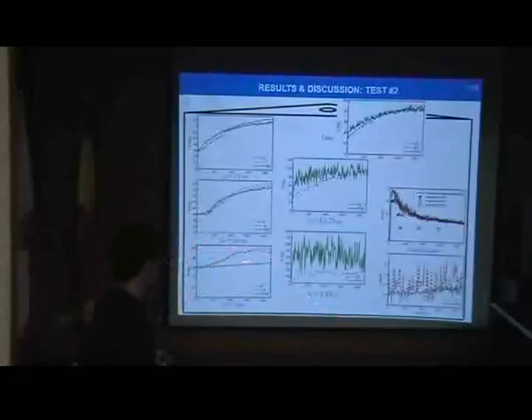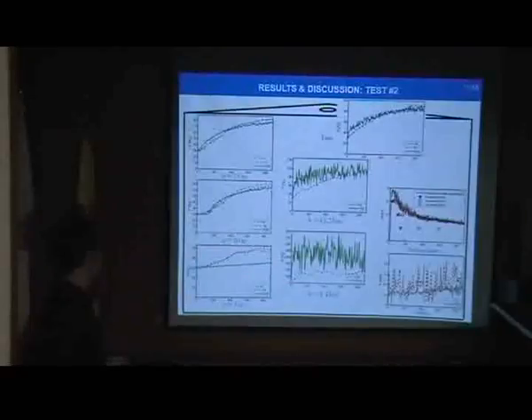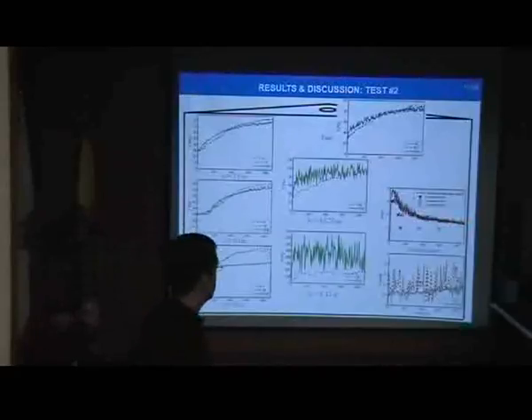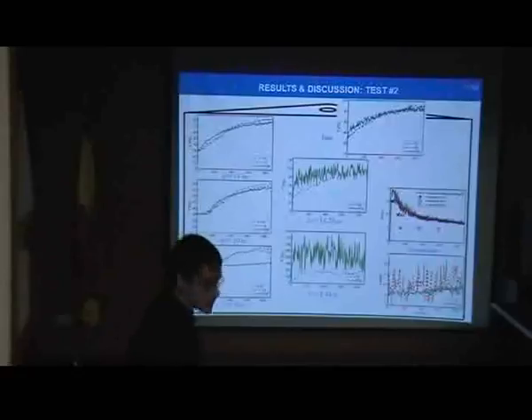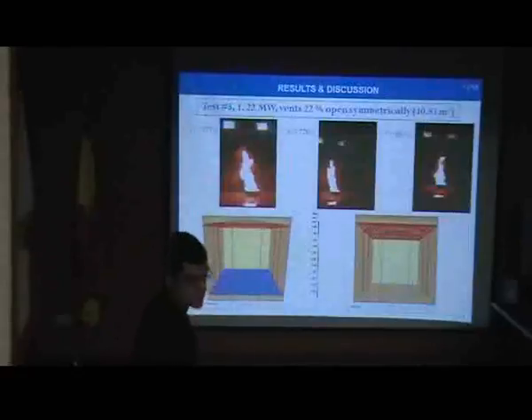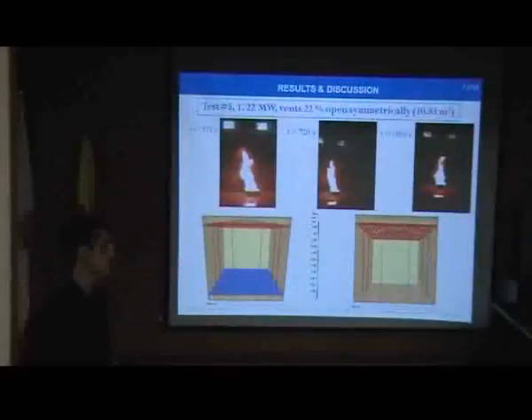However, as happened before, FDS slightly under predicts the smoke temperature at the lowest location near the wall region, and therefore slightly over predicting the final smoke layer height. However, for the measured velocities, quite good agreement has been also observed at the average values during the whole simulation.